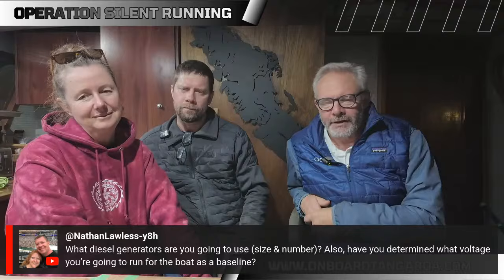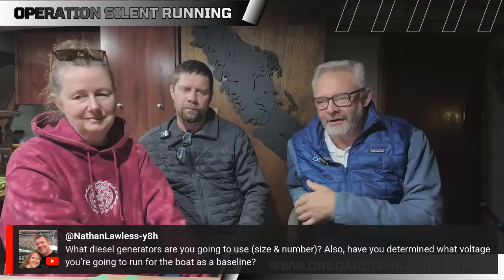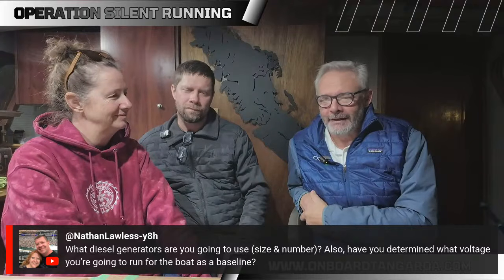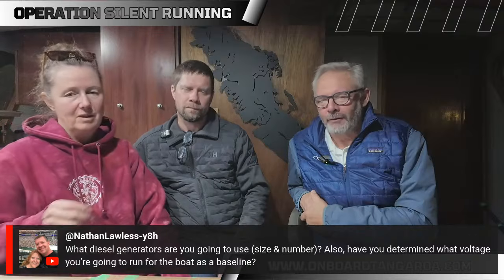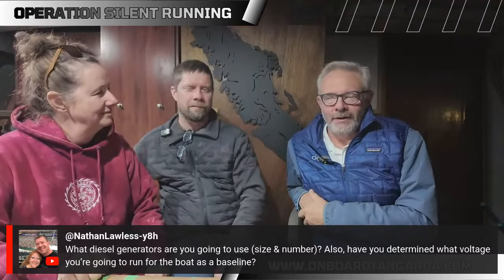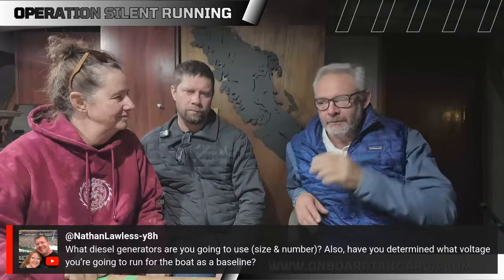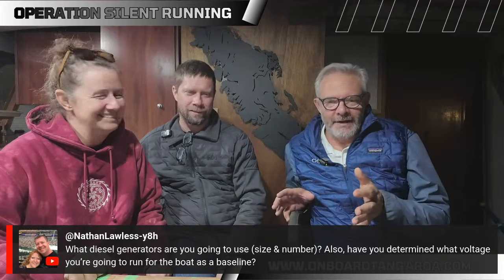But the choice of generator ultimately comes down to efficiency, which is one of the interesting things. Blaine and I have both been shocked at the difference in efficiency between a commercial generator and a retail generator. In the commercial world, a good generator running at constant speed, constant power burns about 190 grams of fuel per kilowatt hour produced. For a bigger one, like 400 kilowatt up to a couple megawatts, that's a happy number to perform at. But when you ask those same generators to run at variable speed, which is the baseline for everyone in the commercial world, they can go up to 270 or 280 grams per kilowatt hour. So the opportunity to save fuel is big, you can save 80 to 90 grams per kilowatt hour, and that's a pretty good rationalization for electrifying a commercial ship.